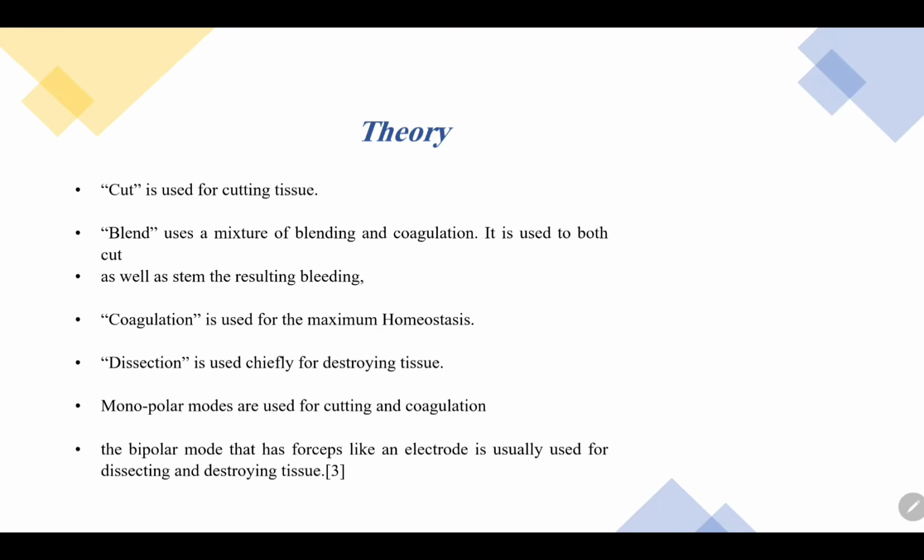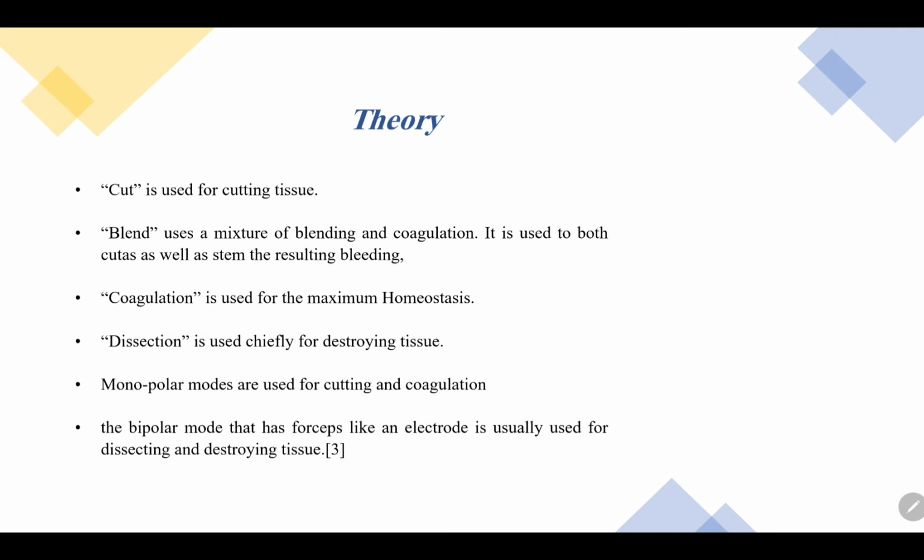In the next slide, theory. Electrosurgical devices are frequently used during surgical operations, helping to prevent blood loss in hospital operating rooms or outpatient procedures. Different levels can be set on the ESU depending on the depth of the cut and the point of the operation.